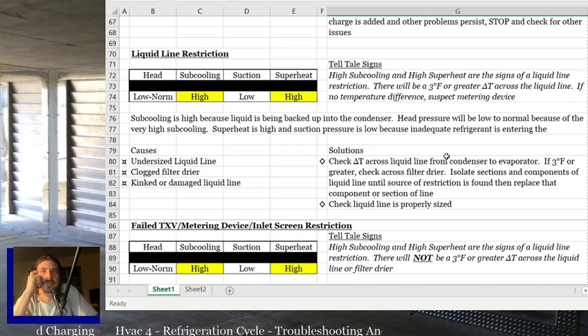So with a liquid line restriction, you're going to have low to normal head pressure. It depends on how big the restriction is what your head pressure is going to look like, but it should generally be low, but it might look semi-normal. Your subcooling will be high. Your subcooling's high because you've got a restriction, so it's going to back up more refrigerant in the condenser.